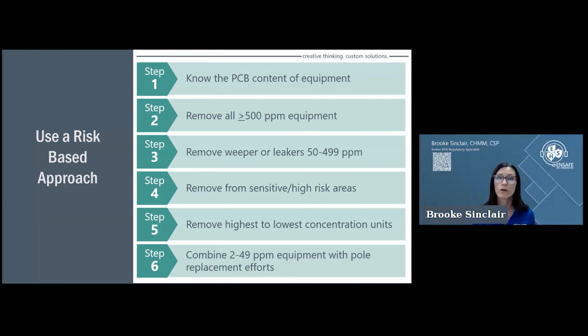The next would be focusing on anything that has had leaks or weeps. And I always think about my sister units as well. So if I have equipment that I've had trouble with, I go and try to find those sister units too, which you can tell by your company numbers, usually what was ordered at the same time from the same manufacturer. And so that's something to think about, because in order to use PCBs, they can't leak. So target those next.